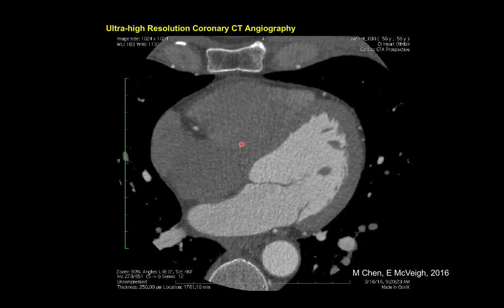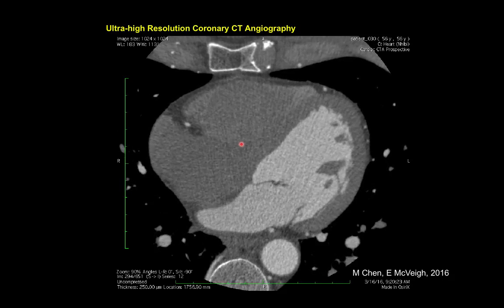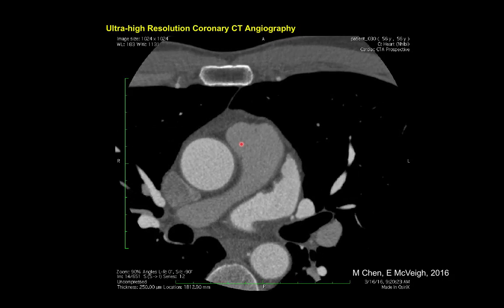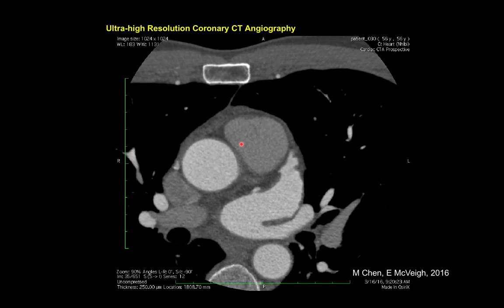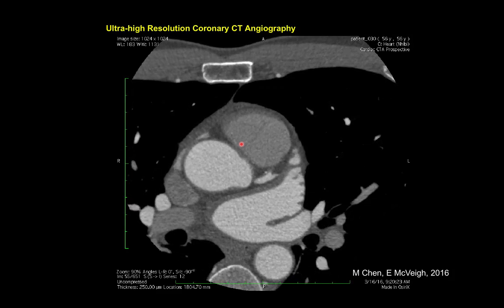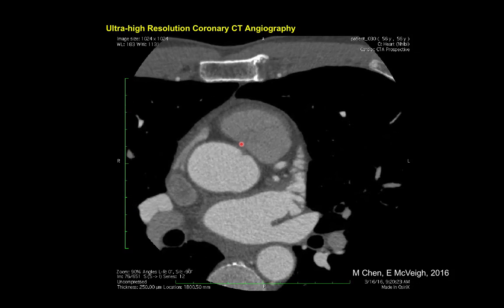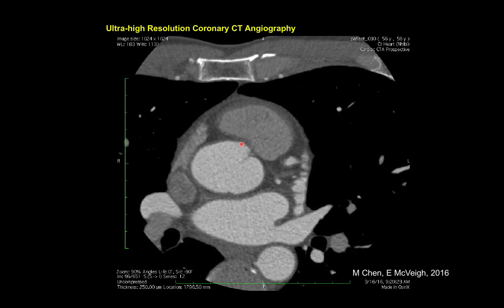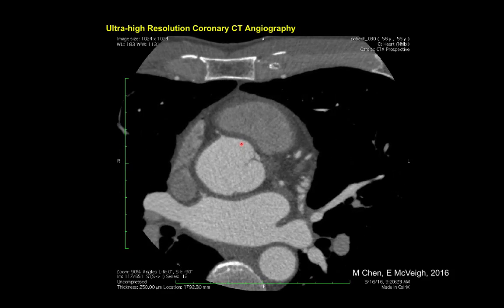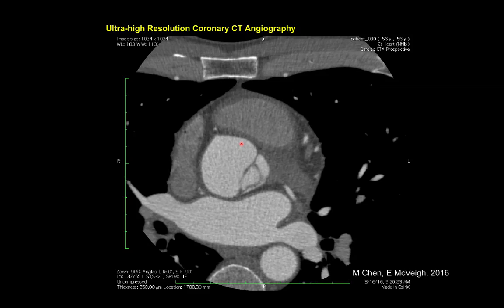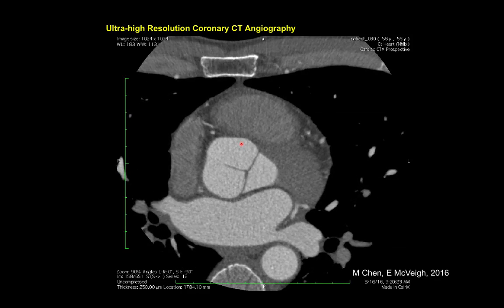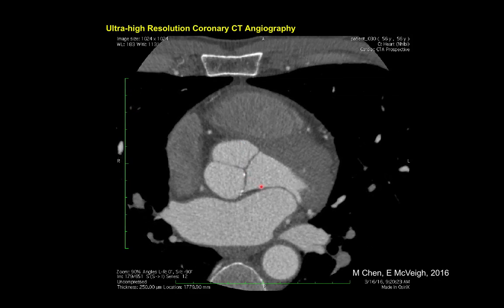So in order to build up those X-rays, we can just slow down the gantry and get more X-rays through. Right? So this gantry, when this image was taken, was rotating at, I think, half a second per 360 degrees, which is about half what a normal cardiac scanner runs at. But ridiculous pictures.